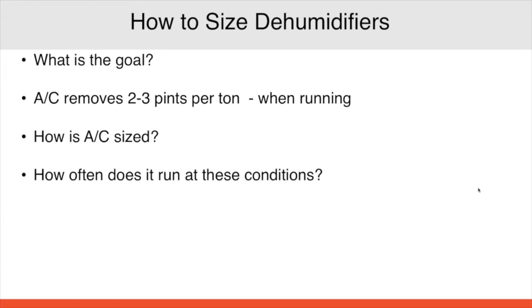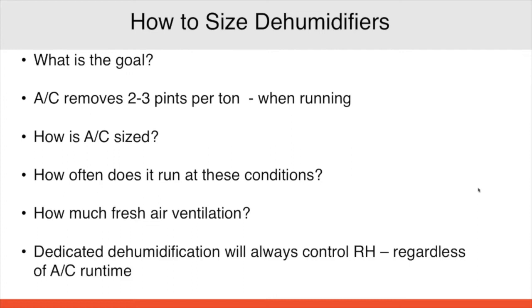Also, how often is it running at these conditions? When we're sizing using Manual J, we're getting peak load conditions. And how often do we run at those peak load conditions? Typically about 1% of the time. So we've got to figure out how we're going to get our latent removal all the other times, when our AC system potentially is only running at that peak load 1% of the time, and we need to supplement that with additional dehumidification. How much fresh air are we bringing in? Based on our climate zone, how much moisture are we bringing into the home, and how are we going to deal with that? 70 and raining, how are we going to deal with all that extra moisture in the air that we're bringing in? And dedicated dehumidification will always control the relative humidity regardless of the AC runtime. So we need to keep that in our minds when we're thinking about our mechanical strategies.